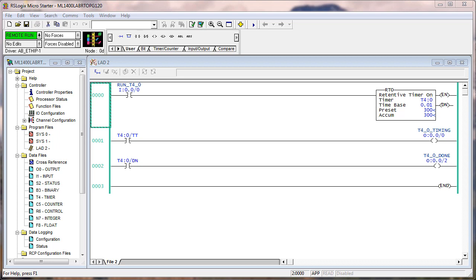Well, when you have 32 bits for your timer data types, you could use 1,000th of a second and have no problem getting up to 32,000 seconds. There is only one timer base. The instructions are what makes the difference, in how the instructions address that timer, that instance of a timer data type.